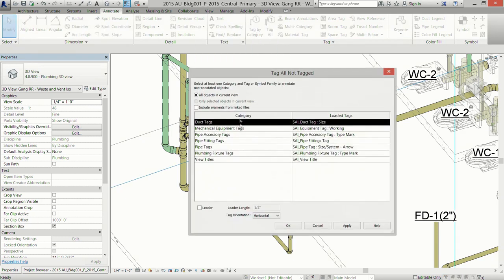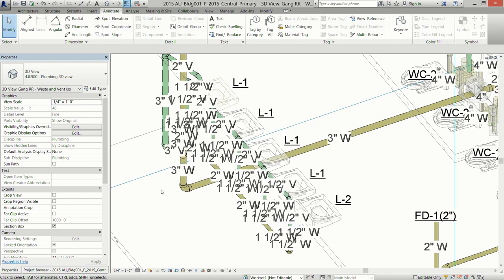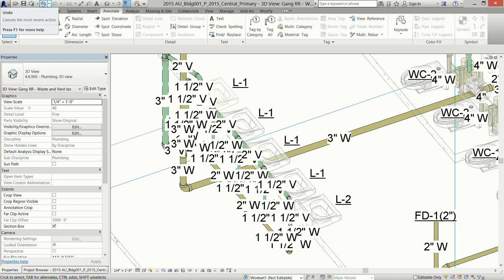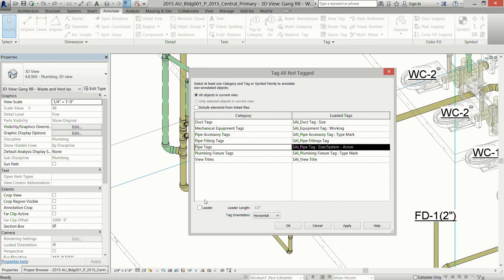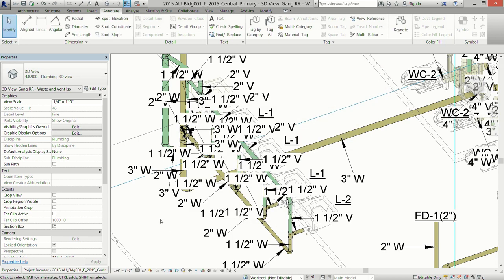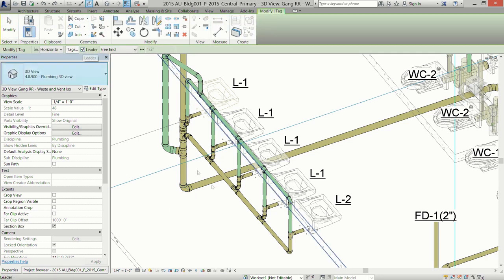The con of using Tag All in an ISO is for pipe tags. If you try it with 'align the tag with the pipe' and no leader, it doesn't work out well — it tags every little transition and piece of pipe. Trying it with a leader is actually worse. You'll spend far more time moving those tags. This is the feature you want to work so badly because you have to tag so much pipe, and if it worked it would save hours — but it doesn't. So you have to go back in and tag pipe manually anyway.